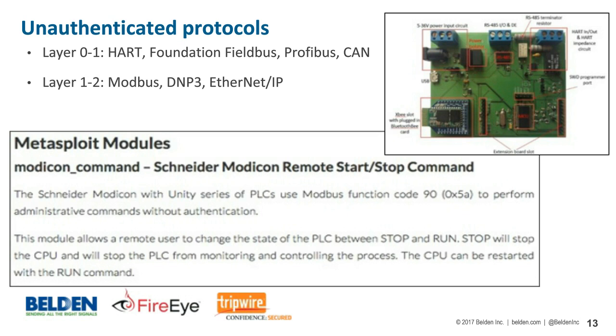This point is absolutely pivotal to get across to people at your board level or your CSO who's never looked at the plant environment before. One example: the Metasploit module for Modicon command remote start/stop. There are several of these Metasploit modules — meaning that just about anyone who has access to this network with this tool, if you're using a Modbus network with Schneider devices, can turn your PLCs on or off.